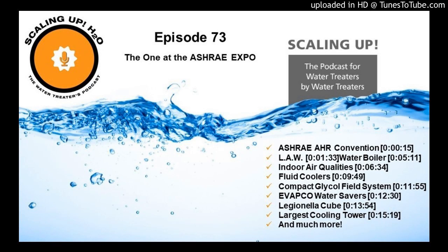Brett, tell the Scaling Up Nation what Evapco is doing new this year. So Evapco Water Systems has just released a new pretreatment system called the Evapco Water Saver, because what it's doing is saving water, reducing the blowdown from our evaporative units. Those evaporative units can usually use 50 to maybe 60% of a building's water. So we're using capacitive deionization to lower the conductivity of that makeup water to the evaporative unit so we can safely increase the cycles of concentration, thus decreasing the blowdown from the unit.